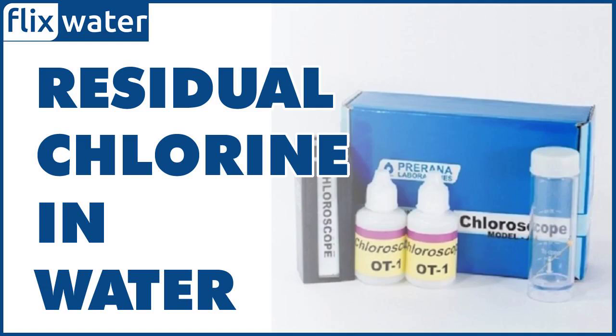levels. The amount of residual chlorine required in drinking water will depend on a variety of factors, including the quality of the water source, the level of contamination, and the specific requirements of the treatment process. In the United States, the Environmental Protection Agency, EPA, sets standards for the maximum allowable levels of residual chlorine in drinking water. The EPA recommends a minimum residual chlorine level of 0.2 parts per million, ppm, to ensure that the water supply remains free from harmful microorganisms.